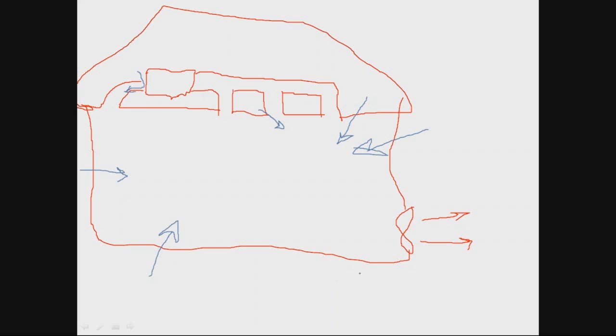So actually if you have a leak in your duct system on the supply side, you'll be blowing conditioned air out into your attic, but also that would cause the entire home to possibly go under a negative pressure that would then draw in outside air through gaps around the windows and doors and things like that as well. So apparently the house is a system. That's what you're telling me.